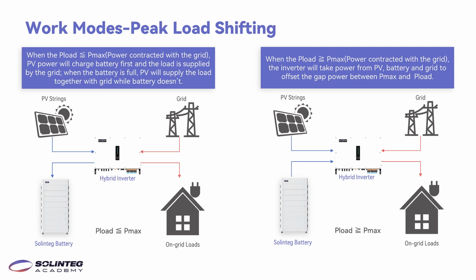This work mode is called peak load shifting, which is used in some places where the grid has regulated the maximum power that you can take from the grid. We call it Pmax. So when the P load is less than the Pmax, the PV power will charge the battery first, and the load is supplied by the grid. When the battery is full, the PV will supply the load together with the grid, while the battery doesn't. And when the P load exceeds the Pmax, the inverter will take power from PV, battery, and the grid to offset the power gap.